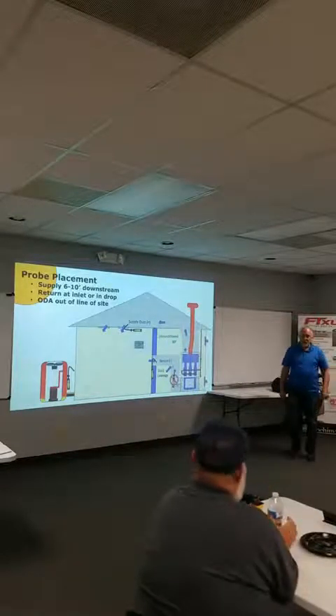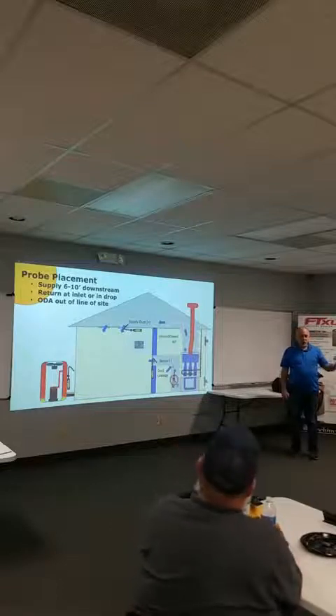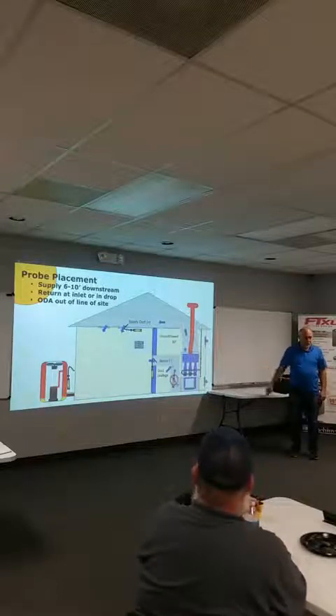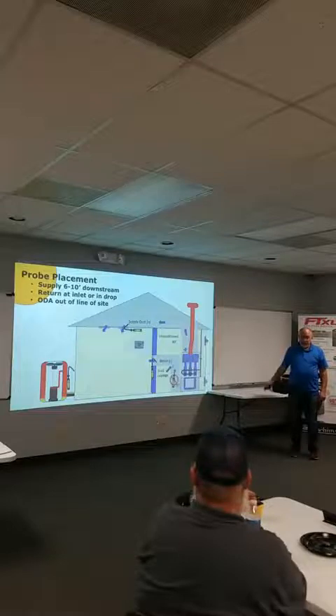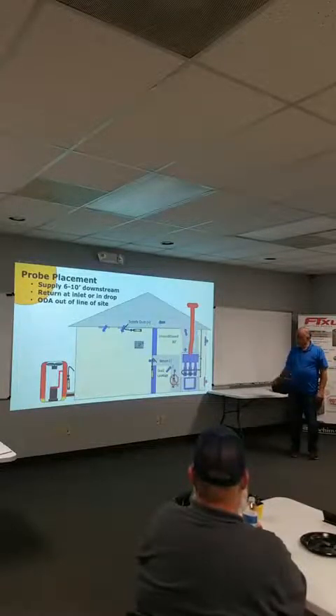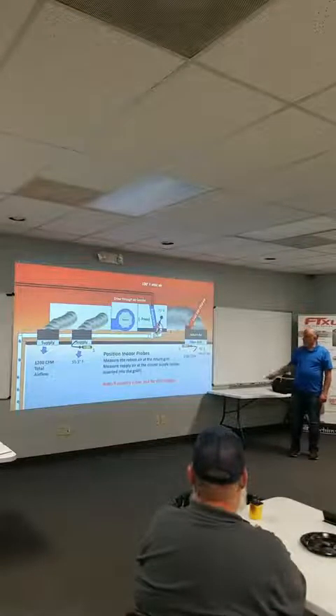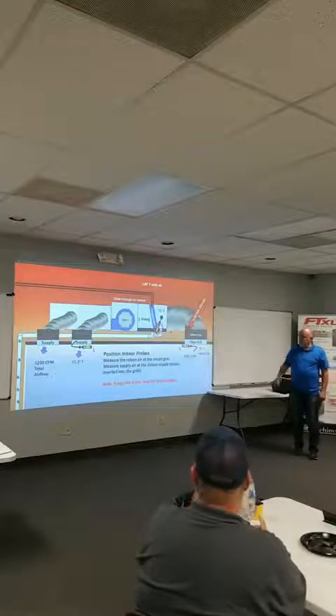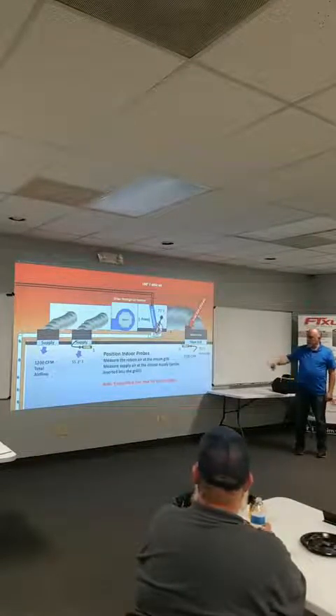If you don't walk downstairs and check the thermostat, if you're always using your jumper wires, you're going to miss this problem. Now, it could be the thermostat's out of calibration too. You can check that against your probe and make sure the thermostat's right. But it could be a problem. All right? Position the indoor probes. We're going to measure at the return air grill and the closest supply.